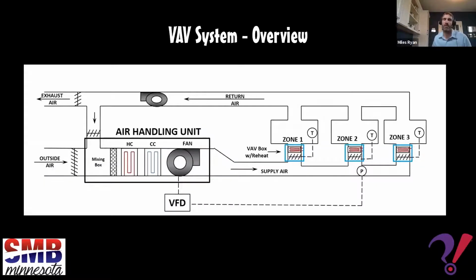First off, we're going to talk about a variable air volume system. So let's just do a quick system diagram discussion here to explain how a variable air volume system would typically operate. In the bottom left, you have an air handling unit. That air handling unit typically has 3 dampers associated with it. It's got an outdoor air damper, which can modulate to dictate how much outdoor air is being brought into the system for ventilation purposes. It's got a return air damper, which can modulate to dictate how much air is being recirculated back from the spaces to be reconditioned and then sent to the spaces again.